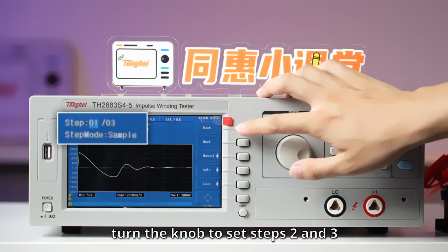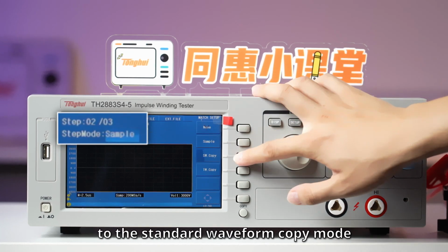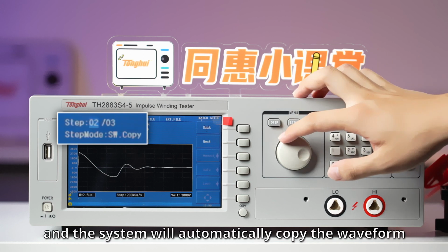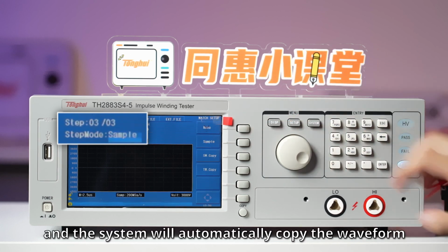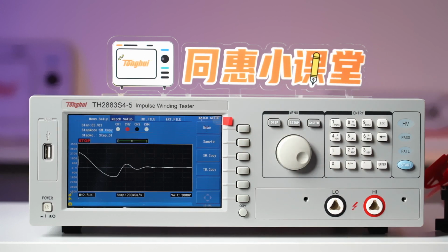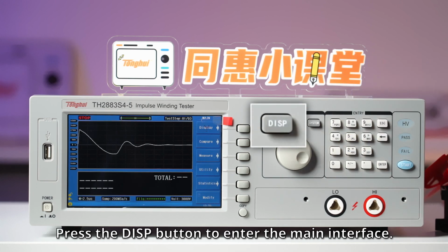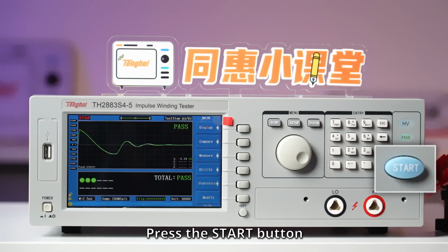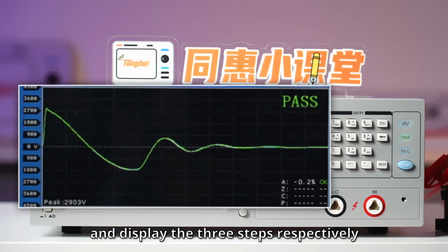Turn the knob to set Step 2 and Step 3 to the standard waveform copy mode, and the system would automatically copy the waveform as Step 1. Press the Display button to enter the main interface. Press the Start button. The instrument will measure and display the 3 steps respectively and compare with the standard waveform.